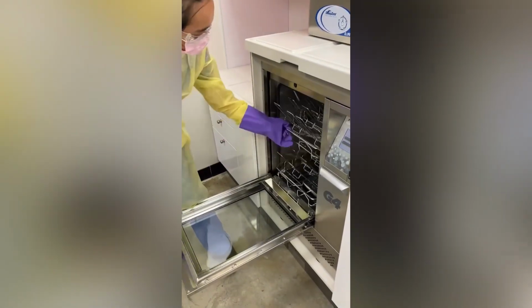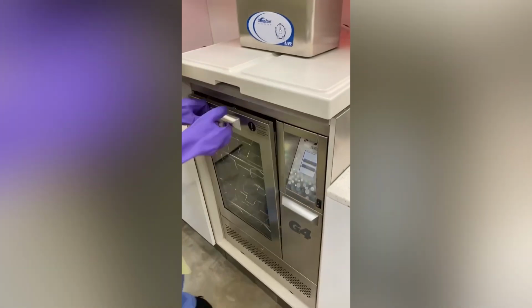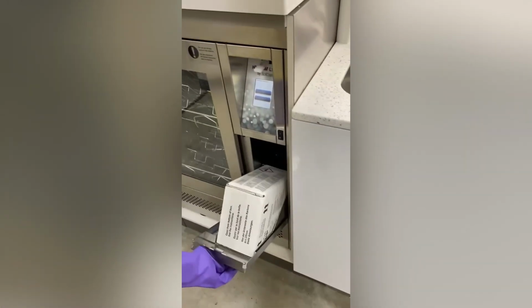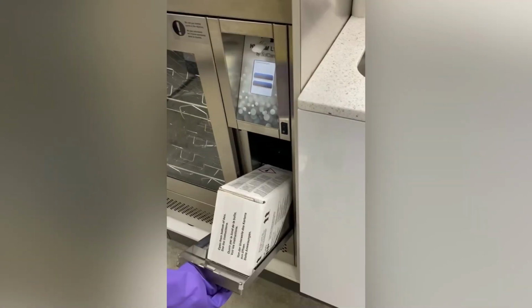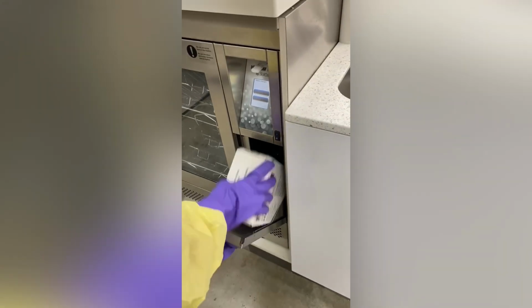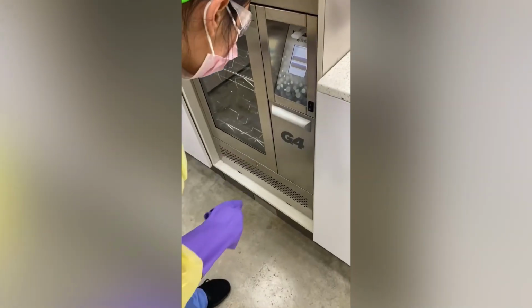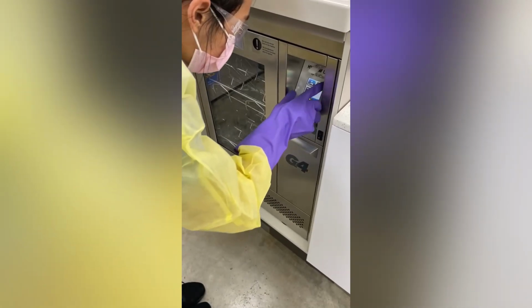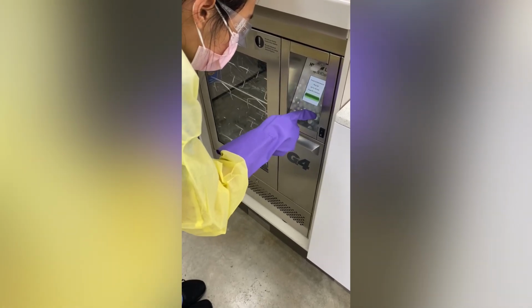The cassette will be cleaned using the Hydrim. The Hydrim utilizes detergent; check to see if it needs to be either refilled or replaced. You can locate the detergent here. The Hydrim runs for 27 minutes and must reach 180 degrees in temperature.